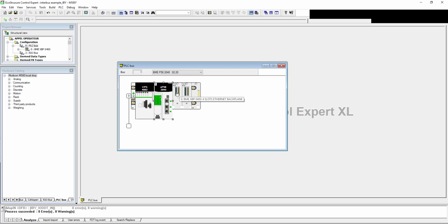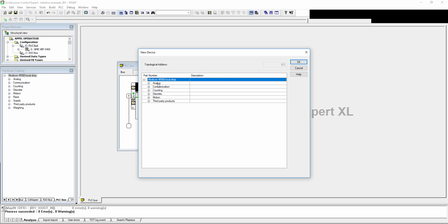The PMEIBS does not have to go in the same relative rack position because the second utility, convert IBY, is going to find out wherever it is in the local rack or in an EIO drop, and then attach those variables to the device DDT and DTM for its new location. So it doesn't have to go in slot 4. In this case, there is no slot 4 technically, you've got slots 2 and 3. So I'll pick slot 2 and insert the PMEIBS hardware.